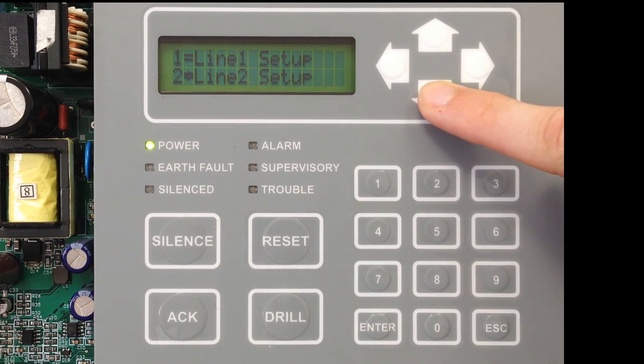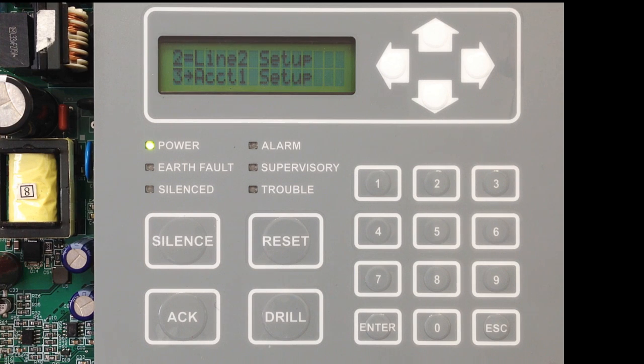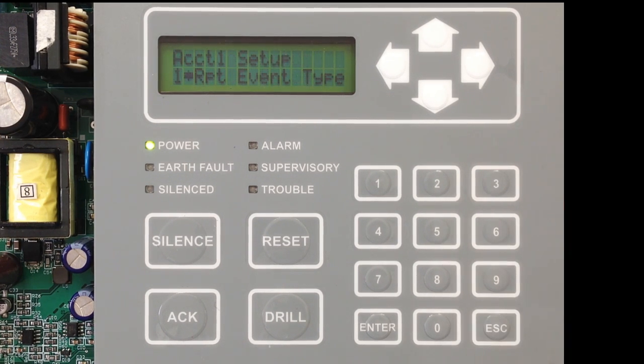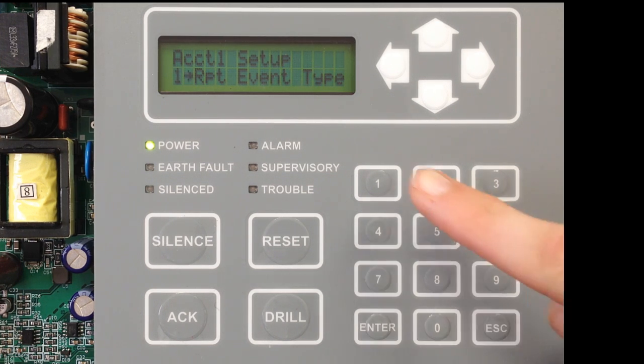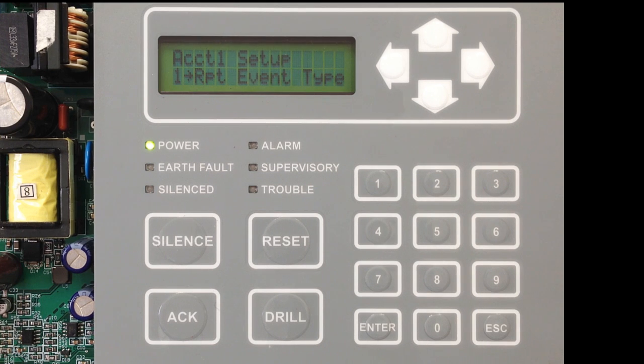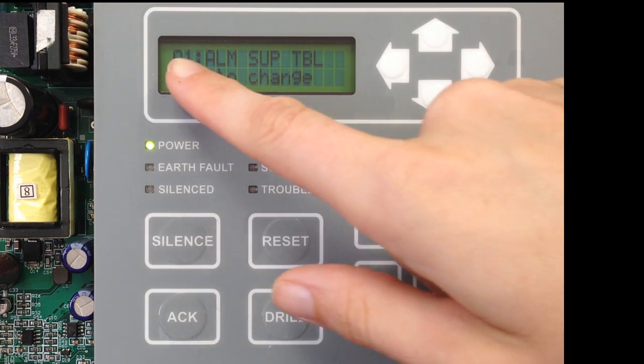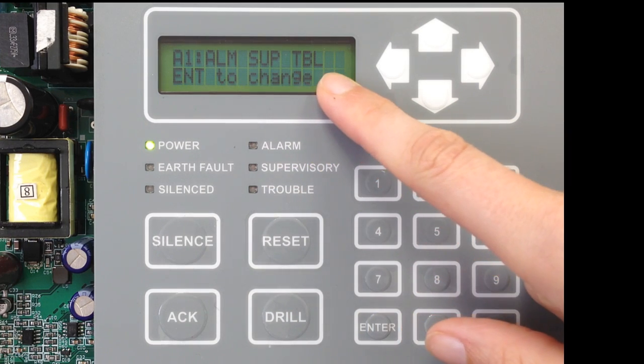Once you've got Line 1 and Line 2 set up, you can go to Account 1 Setup by selecting number 3. In Account 1 Setup, the first thing you can select is the Reporting Event Types. This determines what events you're going to report to Central Station. Your options are Alarm, Supervisory, and Trouble. Currently we are reporting all three — Alarm, Supervisory, and Trouble.